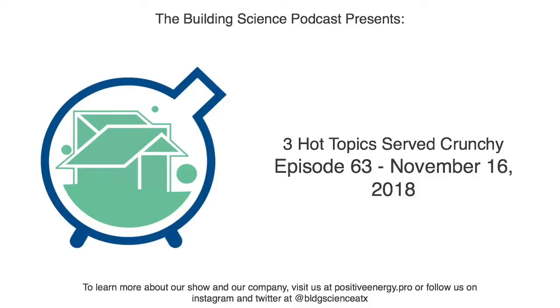So let's see. In terms of packaged heat pump water heaters, the big brand names making them right now are Rheem/Ruud, A.O. Smith, and Bradford White. Bradford White took over the GE line, which was the most popular model out there. But the highest performance equipment that also happens to be the quietest are the newest models from Rheem. They have 50, 65, and 80-gallon models whose manufacturer sound pressure ratings are pretty close to what you would get from an Energy Star dishwasher.